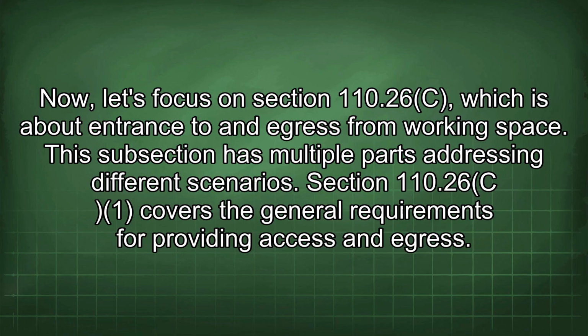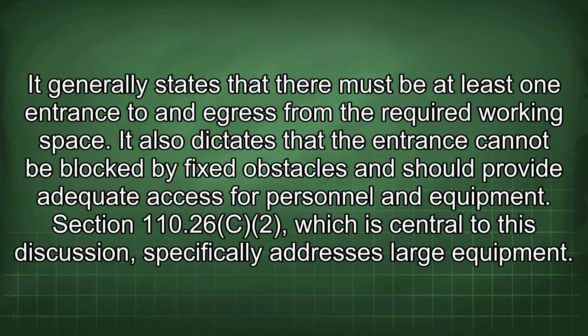Now, let's focus on Section 110.26C, which is about entrance to and egress from working space. This subsection has multiple parts addressing different scenarios. Section 110.26C1 covers the general requirements for providing access and egress. It generally states that there must be at least one entrance to and egress from the required working space. It also dictates that the entrance cannot be blocked by fixed obstacles and should provide adequate access for personnel and equipment.